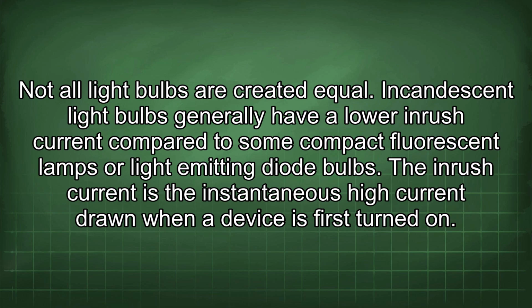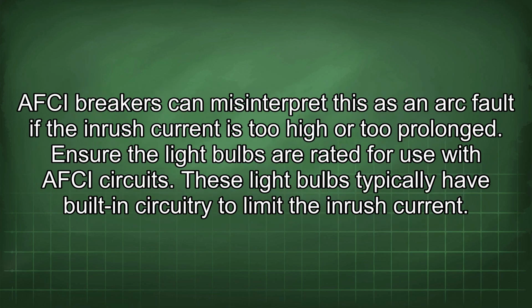Incandescent light bulbs generally have a lower inrush current compared to some compact fluorescent lamps or light-emitting diode bulbs. The inrush current is the instantaneous high current drawn when a device is first turned on. AFCI breakers can misinterpret this as an arc fault if the inrush current is too high or too prolonged. Ensure the light bulbs are rated for use with AFCI circuits. These light bulbs typically have built-in circuitry to limit the inrush current.